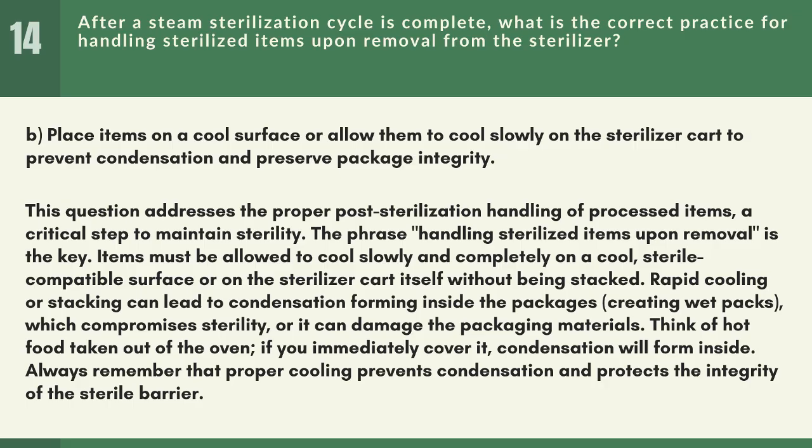Items must be allowed to cool slowly and completely on a cool, sterile-compatible surface or on the sterilizer cart itself without being stacked. Rapid cooling or stacking can lead to condensation forming inside the packages, creating wet packs, which compromises sterility, or it can damage the packaging materials. Think of hot food taken out of the oven. If you immediately cover it, condensation will form inside. Always remember that proper cooling prevents condensation and protects the integrity of the sterile barrier.